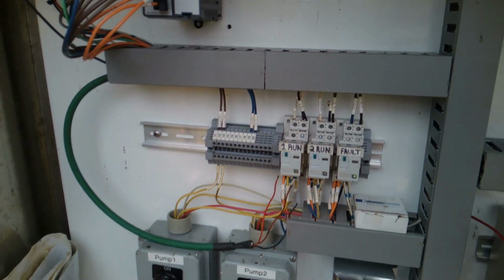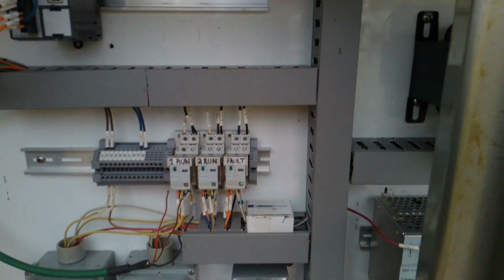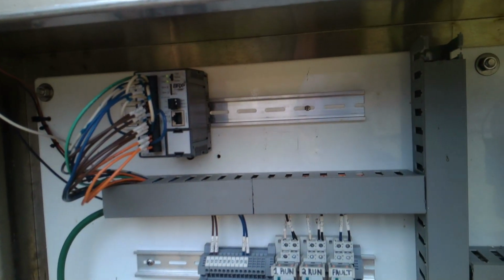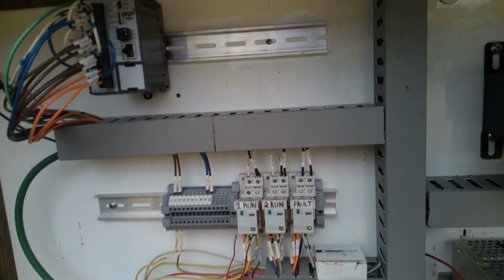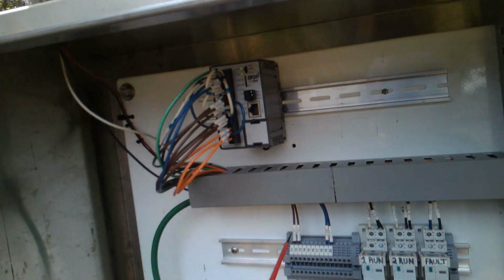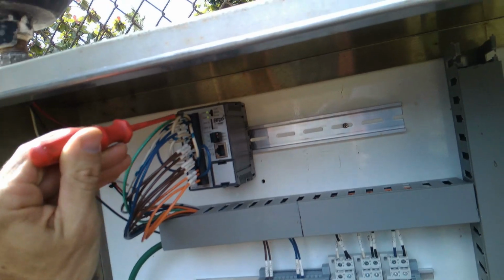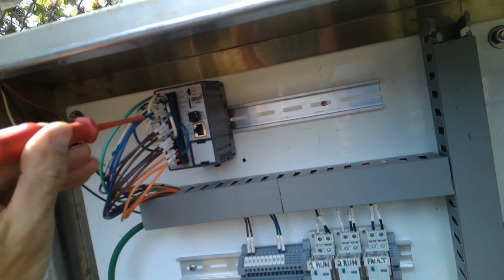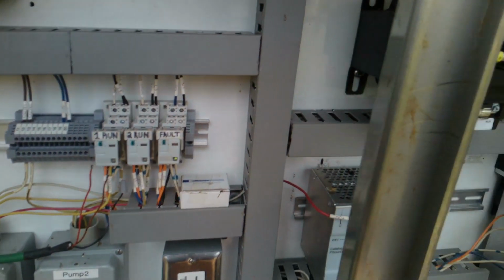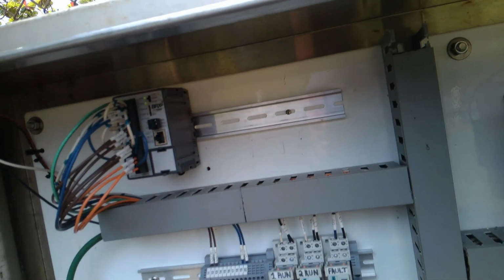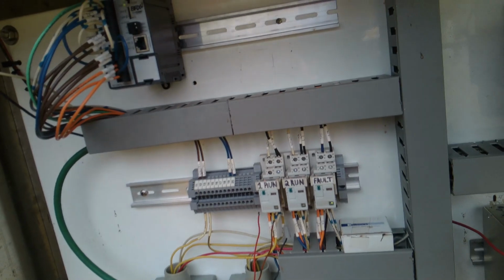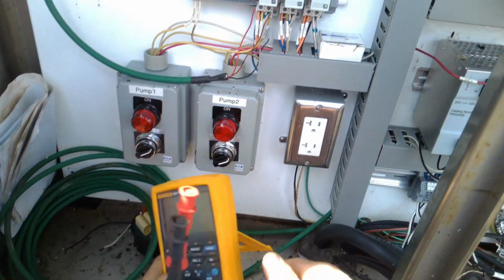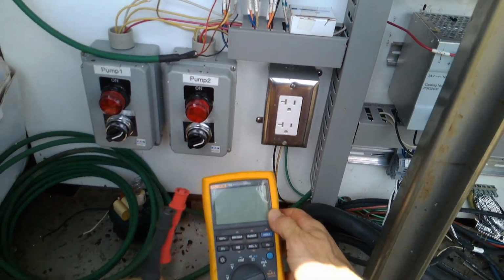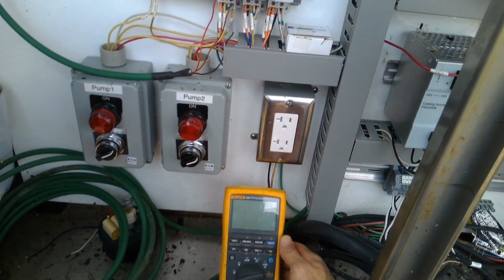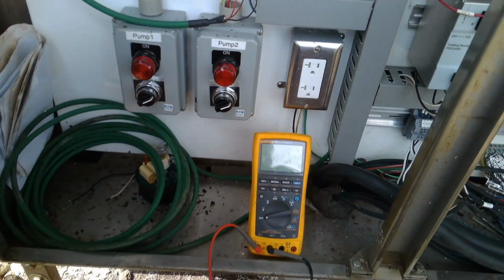Let's put these guys off. Well, no, let's leave them in auto and see if it keeps flickering. I bet that's what it is. Or the transducer is healthy and the PLC's analog input is starting to fail, or there's something inside of him that's starting to fail. So let's get our analog transducer tester. Alright, so we got our Fluke 789.